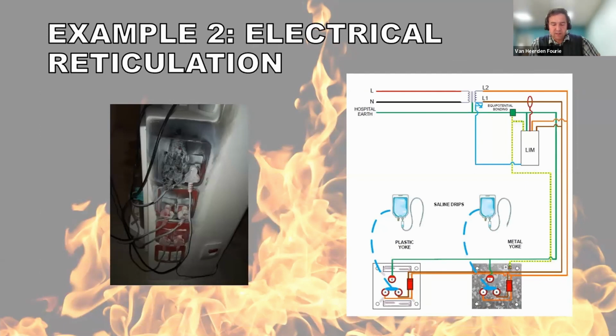Then the second example is about electrical reticulation, which you also mentioned in the introduction, Mohammed. And we found an interesting scenario and a big concern. In our medical locations 1 and 2 areas, power is supplied to the switch socket outlets from a medical isolation transformer, and the earth pin on the switch socket outlet is connected to a line isolation monitor. So if there's any leakage current between live 1 or live 2 and the earth pin, the isolation monitor will alarm. And so what we found with newer installations where the switch socket outlets use a plastic base or yoke, it can actually pose a potential fire risk.